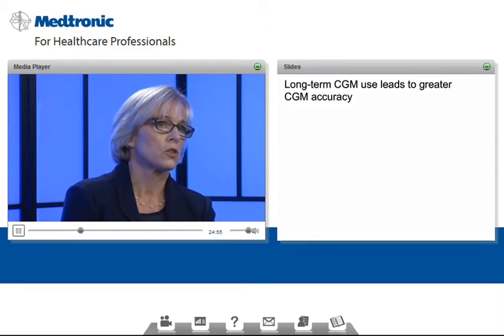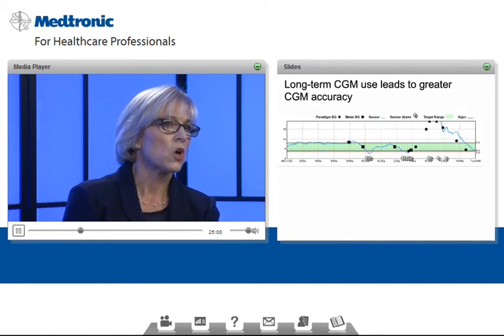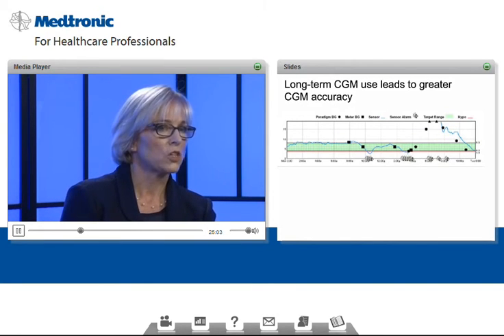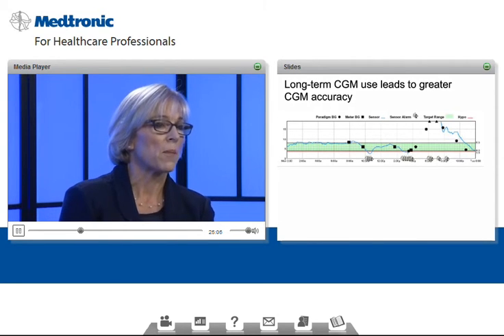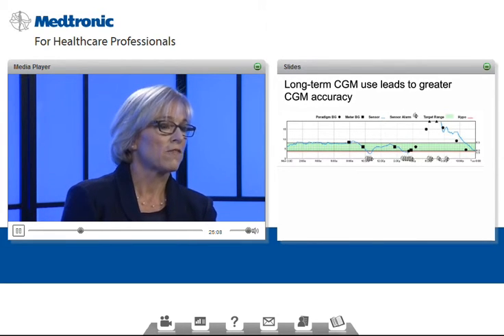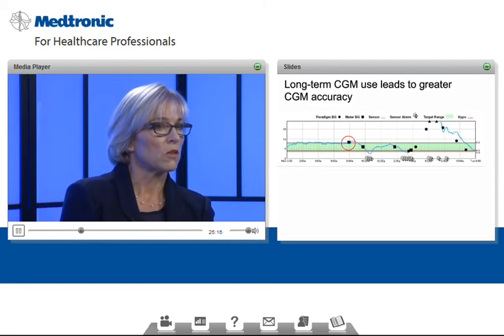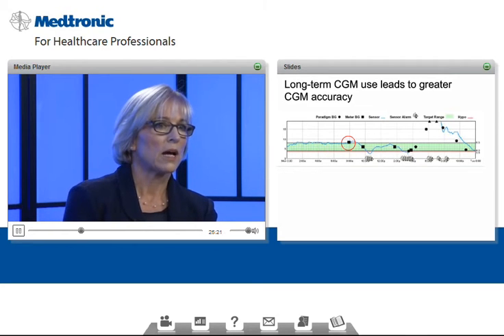We also know that long-term CGM leads to greater CGM accuracy. And if you see here, this was from someone who had just started on CGM and was having challenges with correlating and with doing calibrations, and in fact didn't do calibrations in the required time. The initial readings were quite good through the overnight. It looked like it was going well during the day, and then they hadn't calibrated, and tried to calibrate in the afternoon. At that point the blood sugar was rising, they couldn't get an accurate calibration, alarms started going off, and it's very hard to get a good calibration once the blood sugars have risen like that and it's not stable.